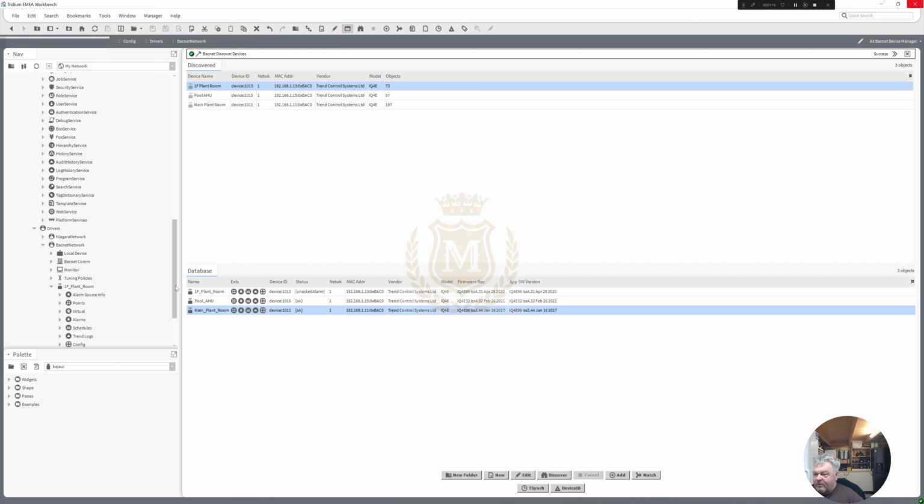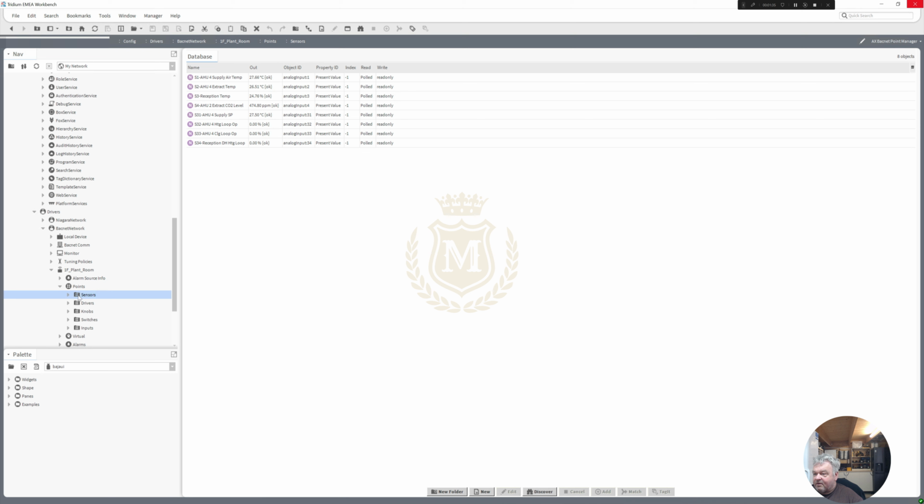So now what I'm going to do is set up the points, check each point that the engineer's done to make sure that they are writable for the knobs, the switches. The sensors and the inputs are just going to be read-only. But let's see what we've got in sensors here. We haven't got that many sensors on this station. We've got some special characters, as you can see, the hyphen there.